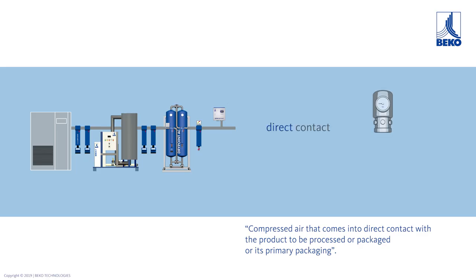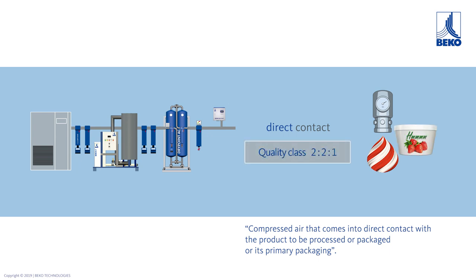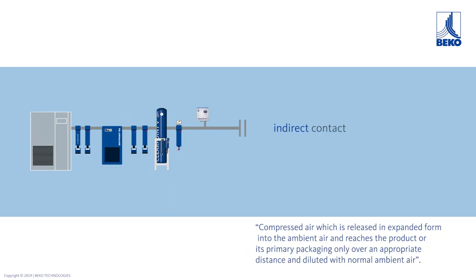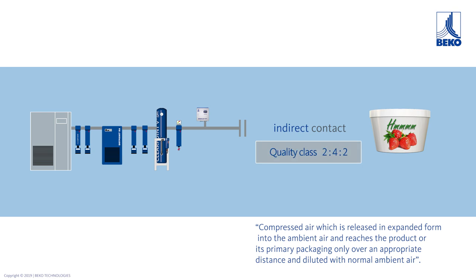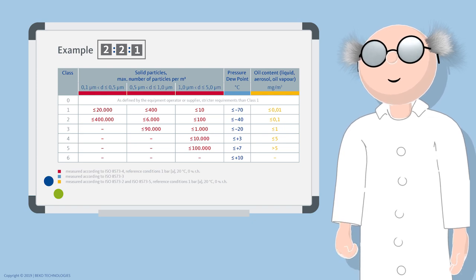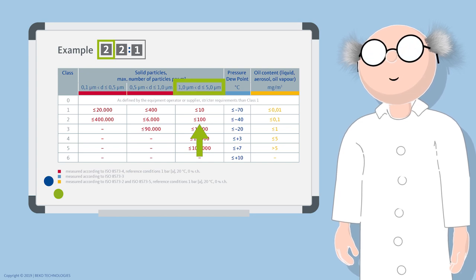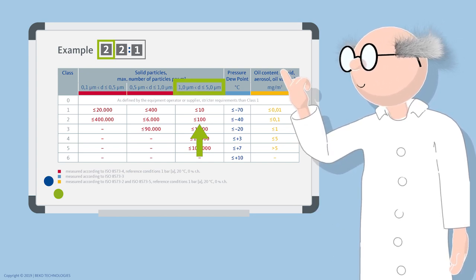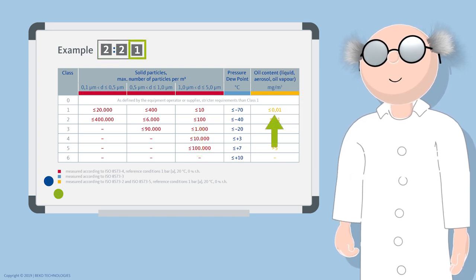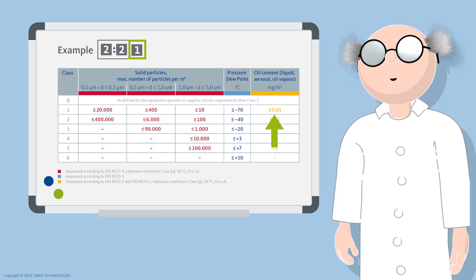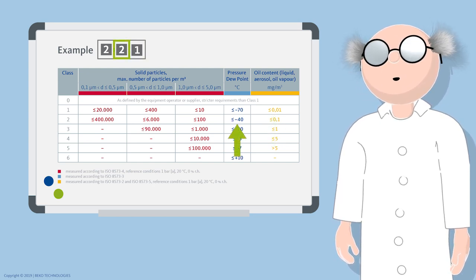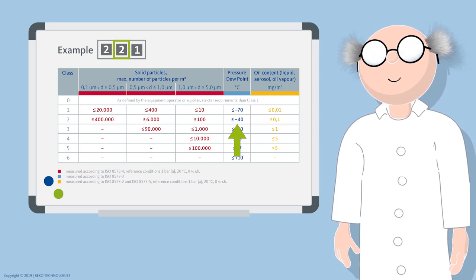In the case of direct contact between product and compressed air, quality class 2-2-1 is recommended. In the case of indirect contact, the recommendation is class 2-4-2. With a compressed air quality of 2-2-1, there may be fewer than 100 particles with a size of 1 to 5 micrometers in one cubic meter of compressed air. The residual oil content is limited to a maximum of 0.01 milligrams per cubic meter, and a pressure dew point of minus 40 degrees Celsius is required.